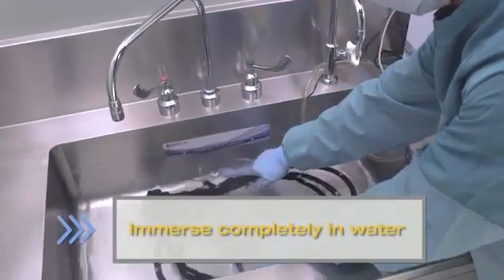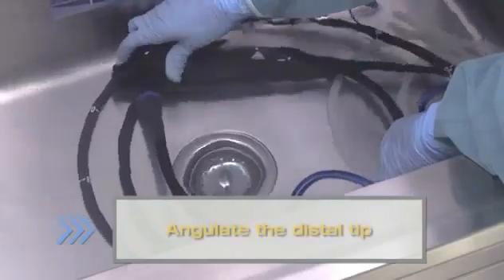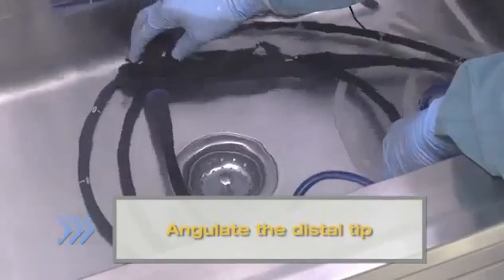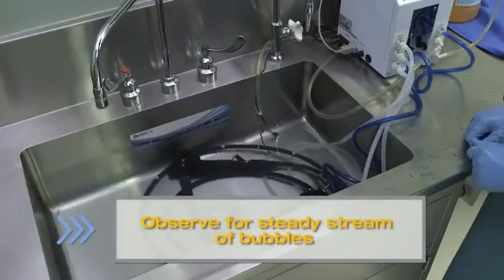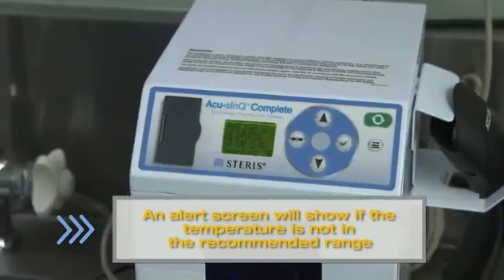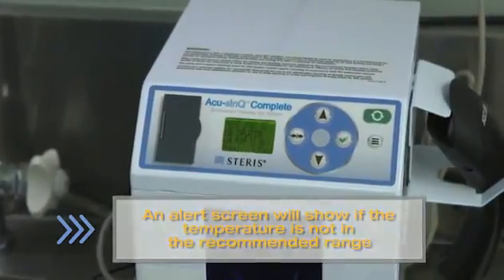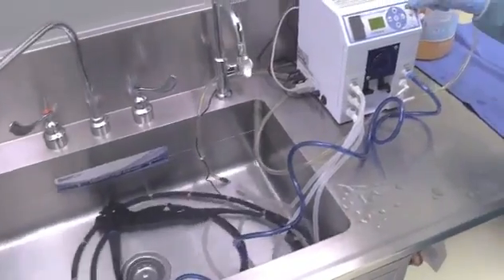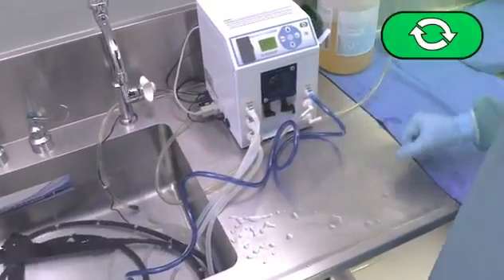Now, immerse the scope completely in water and angulate the distal tip in each direction. Observe for a steady stream of bubbles. Confirm water temperature is within the recommended range for the chemistry IFU. If no bubbles are detected, press Start to end inflation.